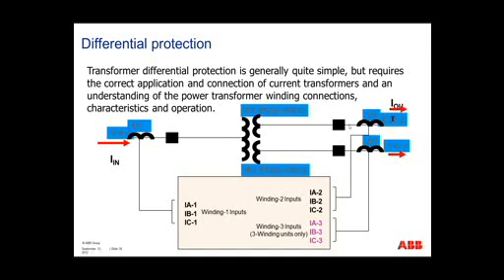Transformer differential protection is quite simple, but there are several aspects you need to take into account, especially if you're not using microprocessor-based relays. If you're using non-microprocessor-based relays, because of the turns ratio, you need to account for tap settings and the phase shift that the transformer poses on the system.